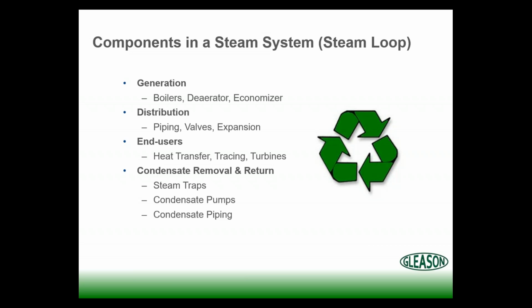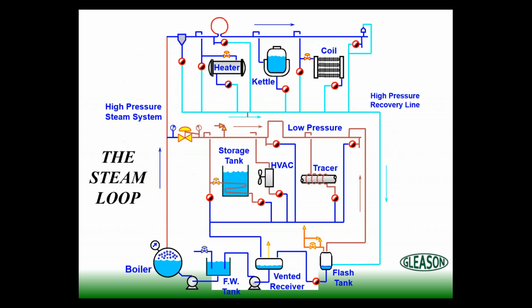So again, that's another incredible advantage of steam. When I talk about the steam loop, here's just a diagram where we talk about the generation phase, which is here in the boiler plant or boiler room. So we're generating that. We distribute that. We get it to where we want to use it. And here's some of our end users. Here's a coil, could be in an air handling unit up on the roof, or a kettle, or a cooker. And it could be in the cafeteria or the kitchen, or at a food and beverage facility. Water heaters, storage tanks. There's a unit heater that could be up in the corner of the warehouse or the shop. And some of that steam tracing we talked about in those outdoor applications.